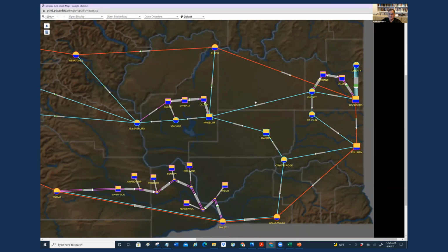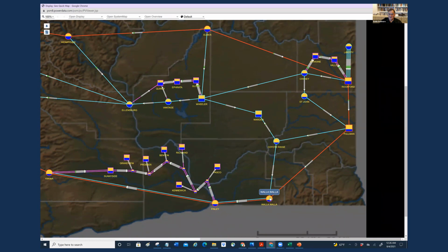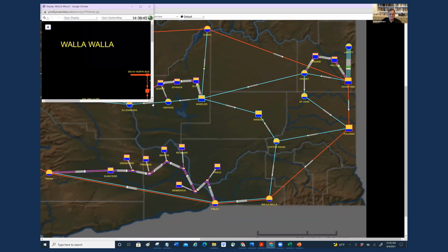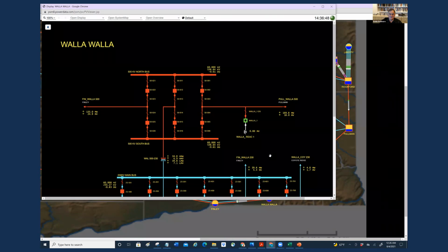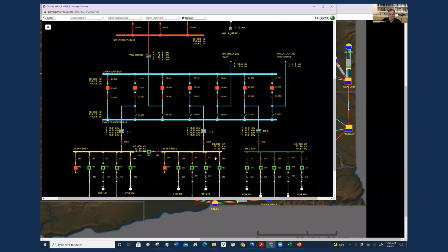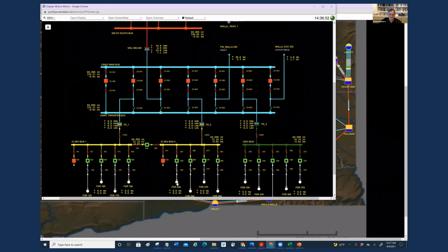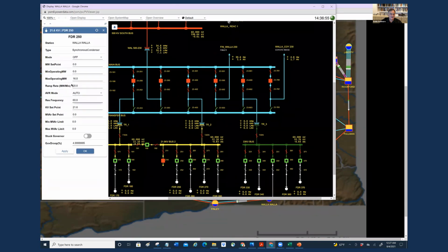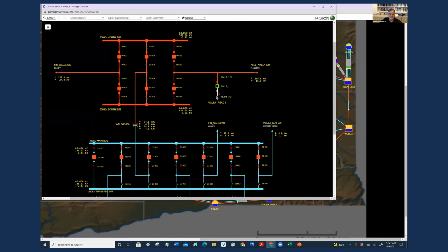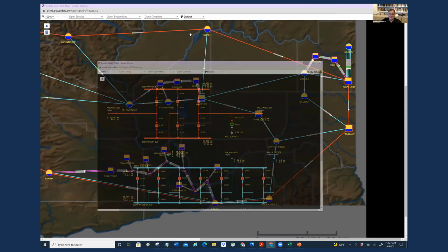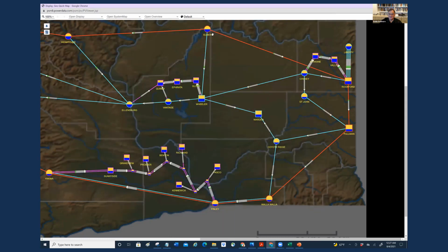The other station we'll be looking at operating a reactor is at Walla Walla. At that station, we have some wind turbines that are all offline. These units are all relatively small, about 16 megawatts. But there is a reactor there, a fairly large one, of 250 megavars. So the question is, if I switch these reactors in or out of service, what sort of voltage can I expect to see change at that substation?